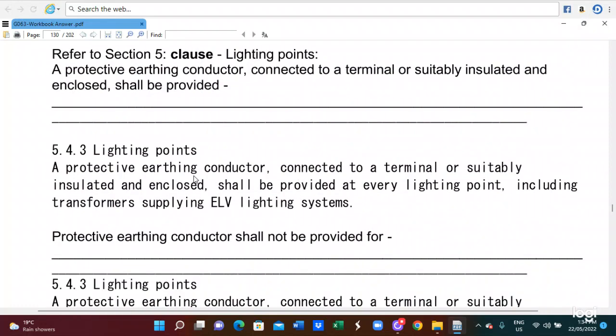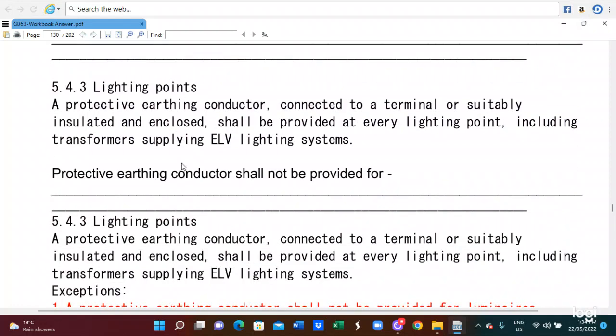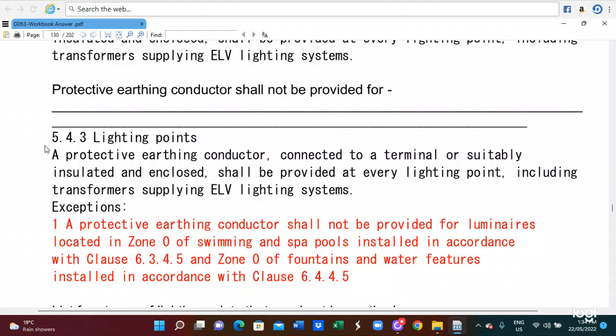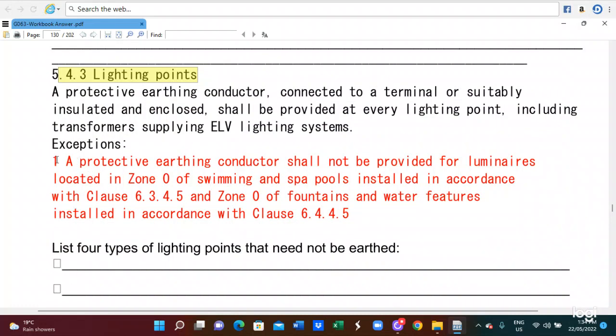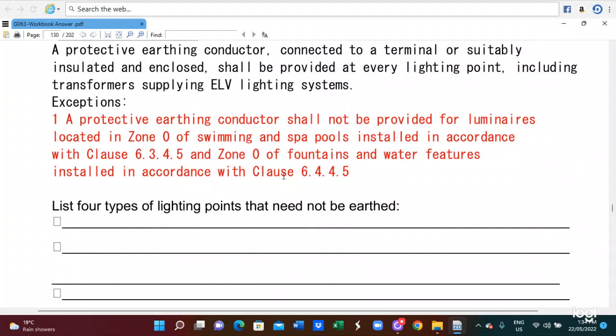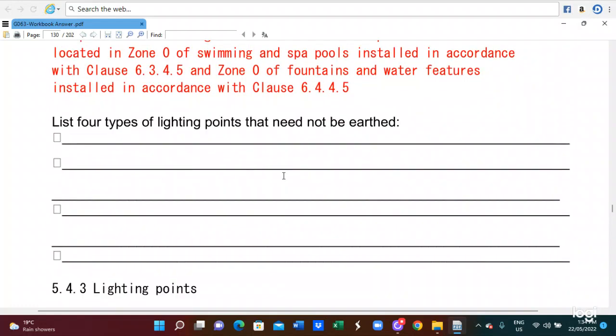And also 5.4.3 is the lighting point connection, a protective earthing conductor for the lighting point. 5.4.3, you can see the lighting point. A protective earthing conductor shall not be provided for a luminaire located in zone 0 of a swimming pool, installed in accordance with clause 6.3.4.5, and zone 0 of a fountain or water feature installed in accordance with clause 6.4.4.5.